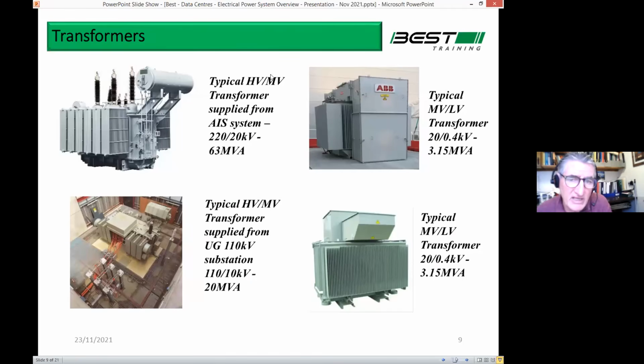Then transforming down, I'm showing 4 different types of transformer here. The top one is where you transform from high voltage down to medium voltage. High voltage, just to remind you, in Ireland is either 220 kV or 110 kV. There's also 38 kV on our system, but I don't think there are any data centers connected at 38. I think most of them are connected at 110, and the Facebook data center is 220 kV. So that's what you have there.